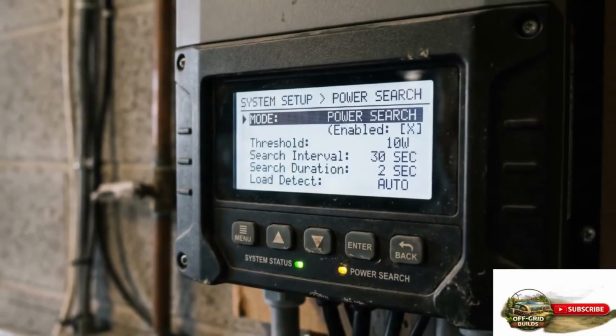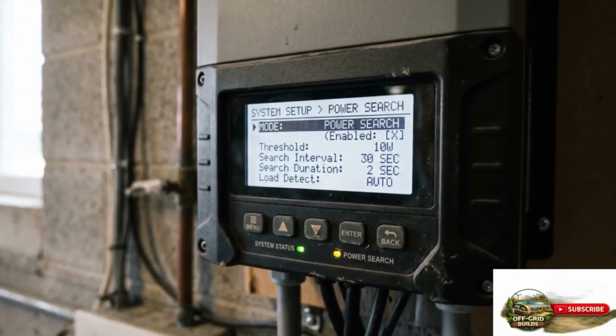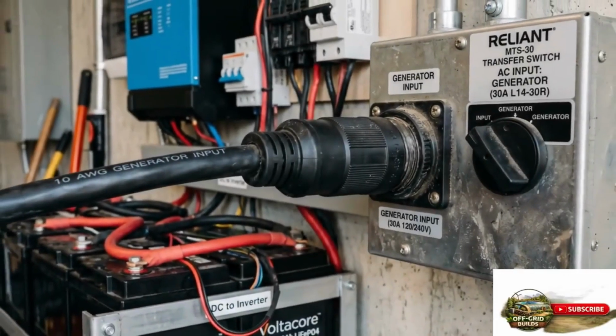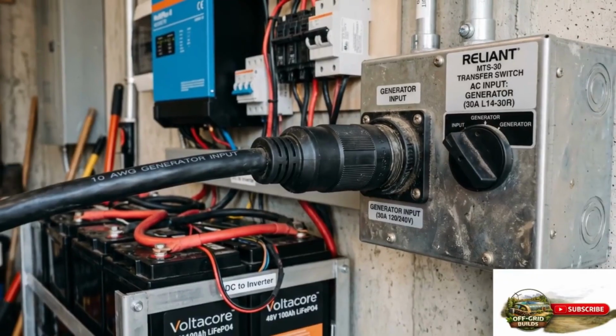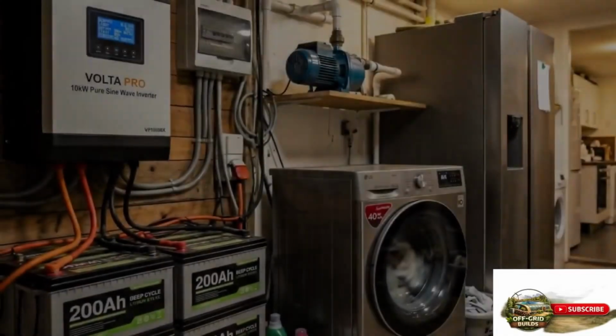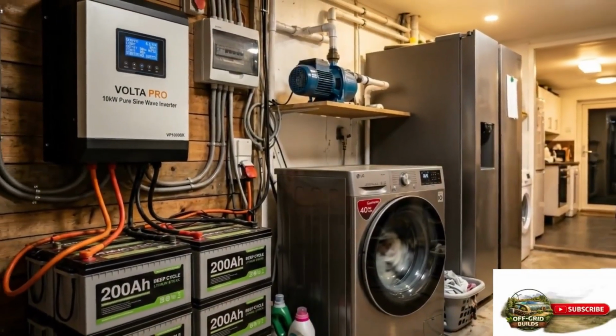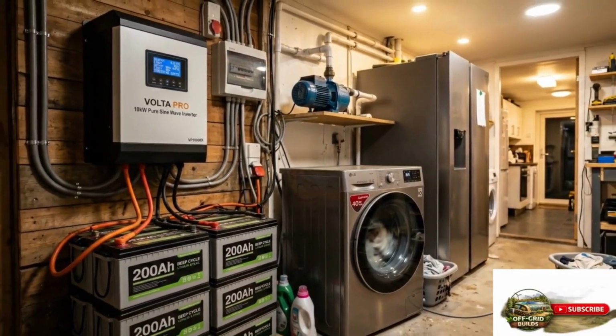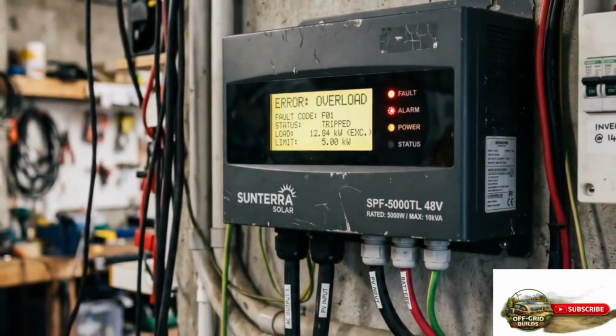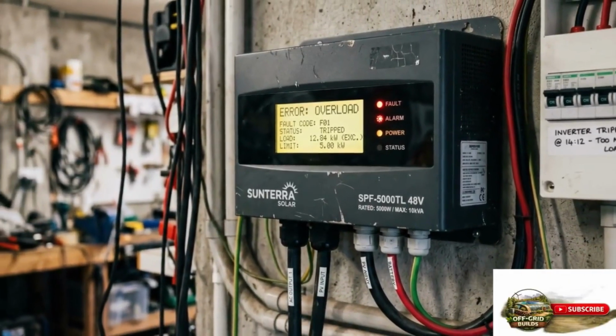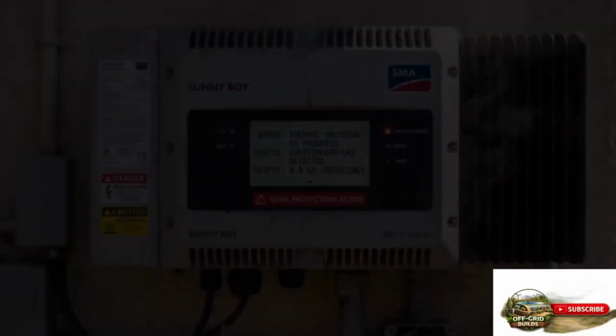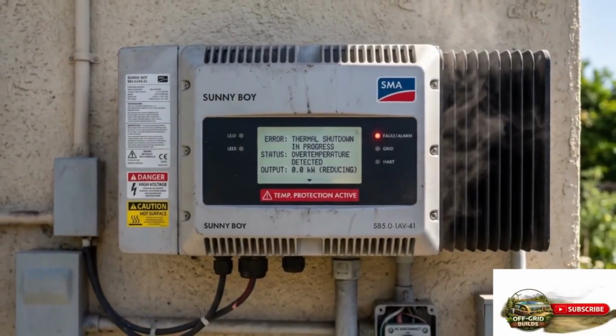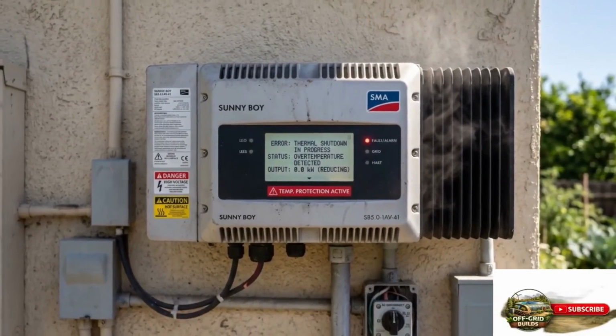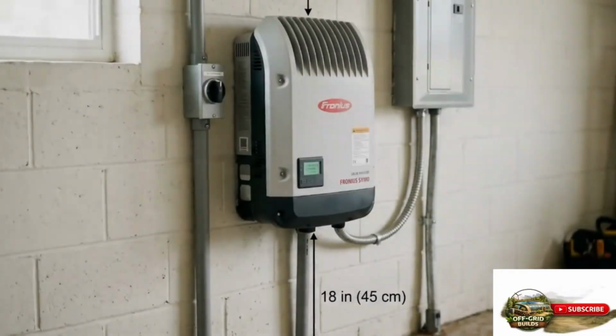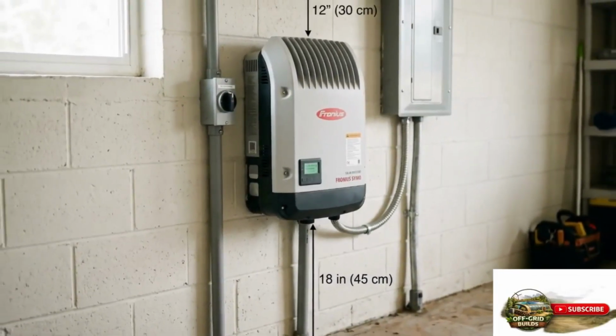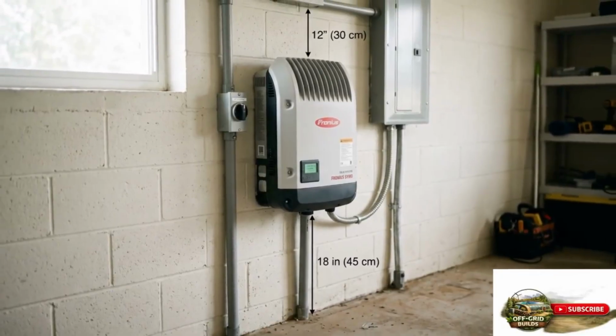For any system serving a full household, pure sine wave inverter output is non-negotiable. In 2026, quality pure sine wave off-grid inverters in the 8 to 12 kilowatt range are available from Victron Energy, SMA, Schneider Electric, and several other manufacturers. Victron Multi-Plus or Quattro series inverter chargers, which combine inverter and battery charger functions in a single unit and allow for AC grid or generator pass-through, are among the most commonly specified units in serious off-grid installations in 2026.